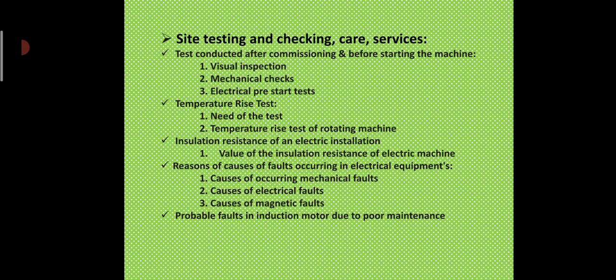Next, the temperature rise test. This is a type test. This test is not performed on all the machines but is performed if found necessary. In this test, the rise in temperature is measured after the machine runs at full load for some time and the final temperature is reached and has become constant. This final temperature rise should be within the limit for the class of insulation used.